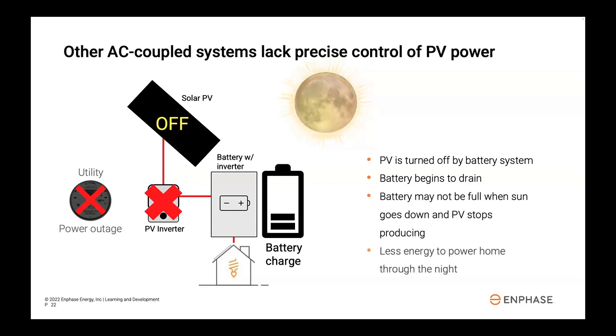With AC coupled systems, once the battery gets down to a certain state of charge, typically around 80%, it'll use frequency shift to try to turn the solar system back on again. If there's enough sunshine, it will turn on and begin recharging the battery. The risk to the homeowner is that they could potentially be left with an 80% charged battery at the end of the period of the day when the system could charge the battery, leaving only 80% of the storage capacity available to power their home during that blackout.